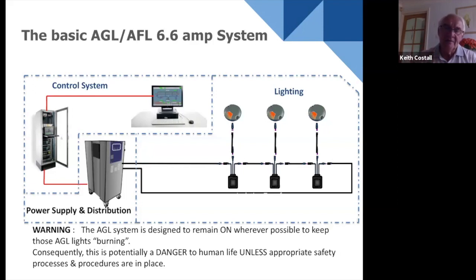Now, the intensity levels are defined by ICAO as 5 steps for runway. That is 100% of light output in accordance with the isocandela diagrams. 100%, 30%, 10%, 3%, and 1% as a percentage of light output. But the Aerodrome Design Manual from ICAO, part 4, there's some graphs in there, and there's a tolerance range. So ICAO's percentages are at the top of the tolerance range, but if you look at the current values that are in the IEC technical specification or in the FAA advisory circulars, they are at the bottom of the range. So there is a tolerance, and you must be aware of that.